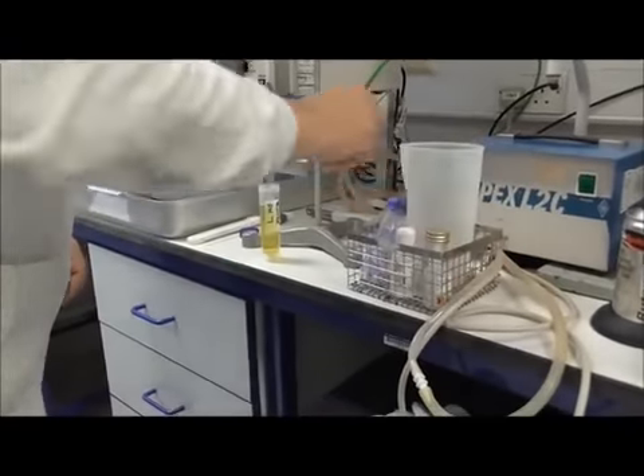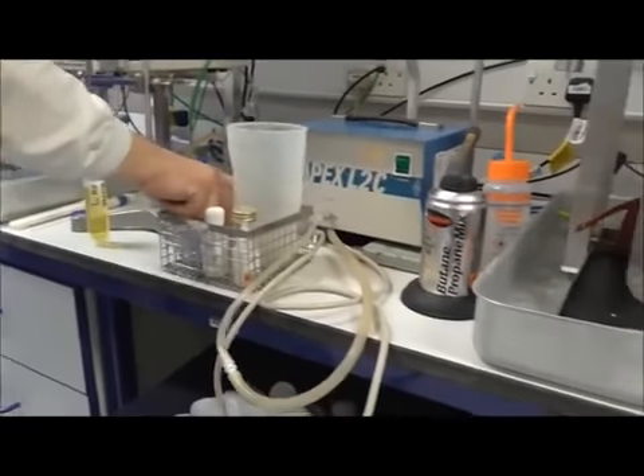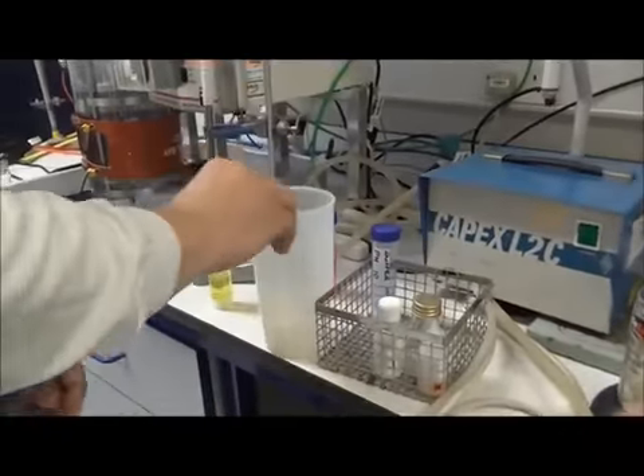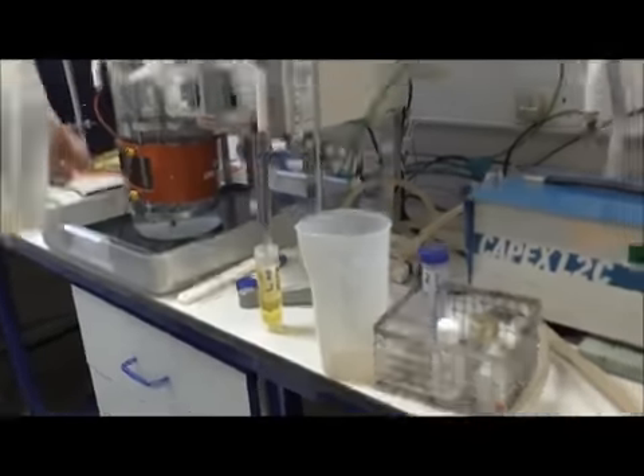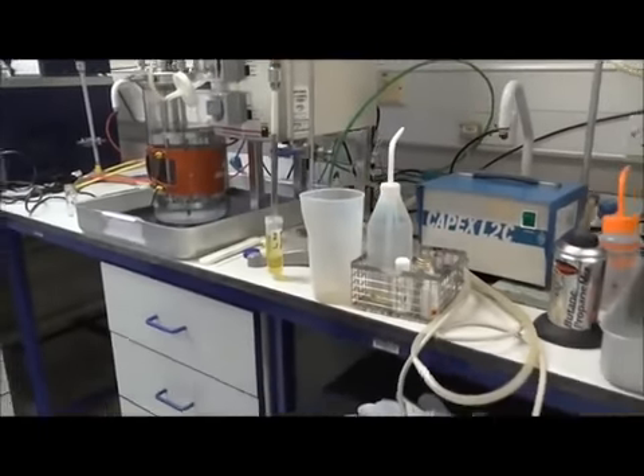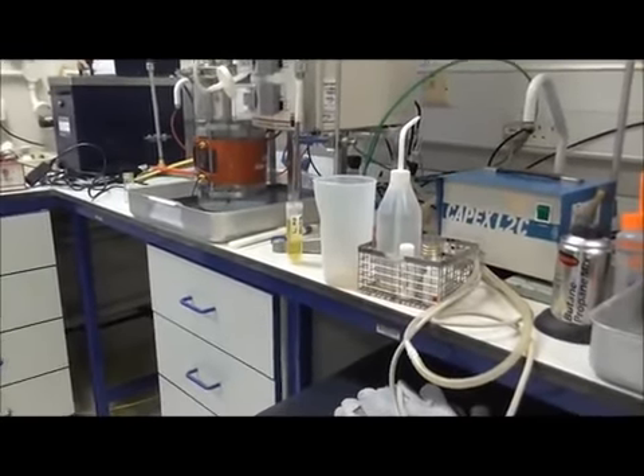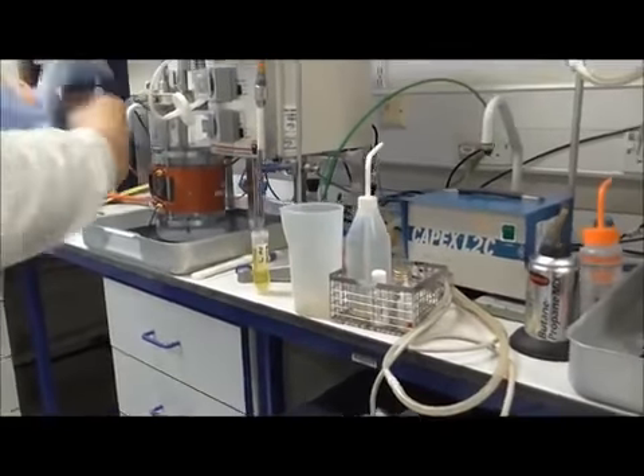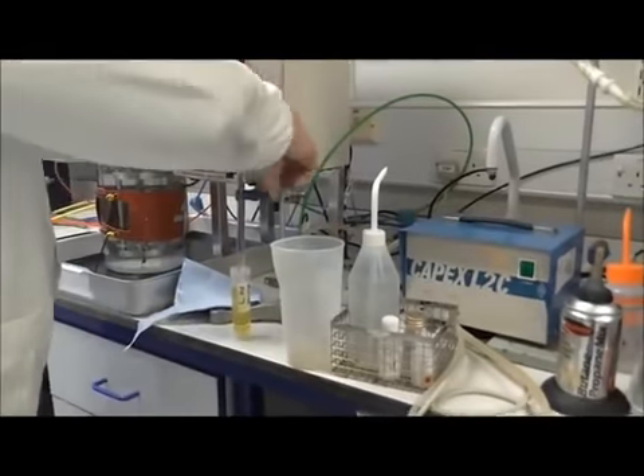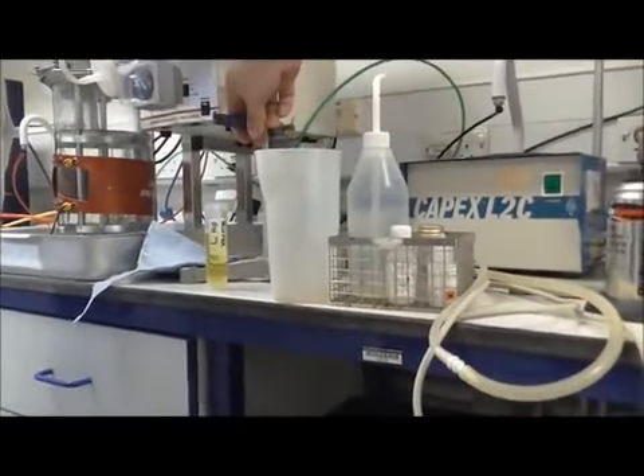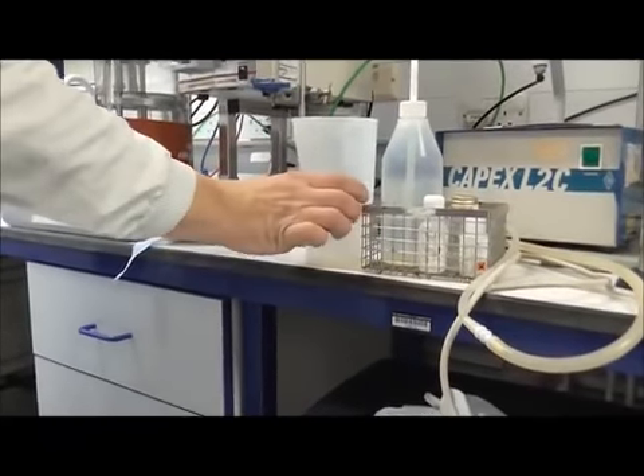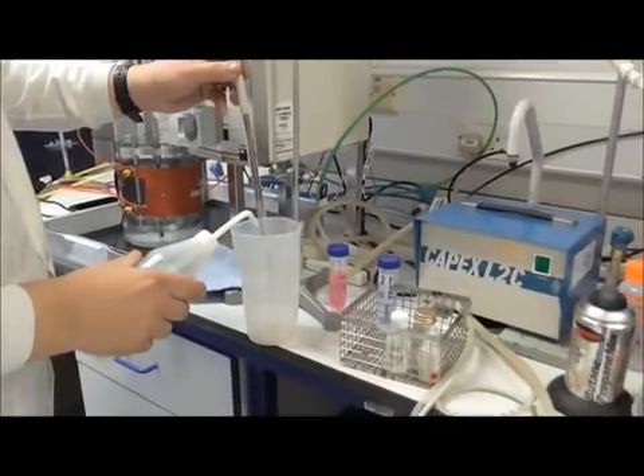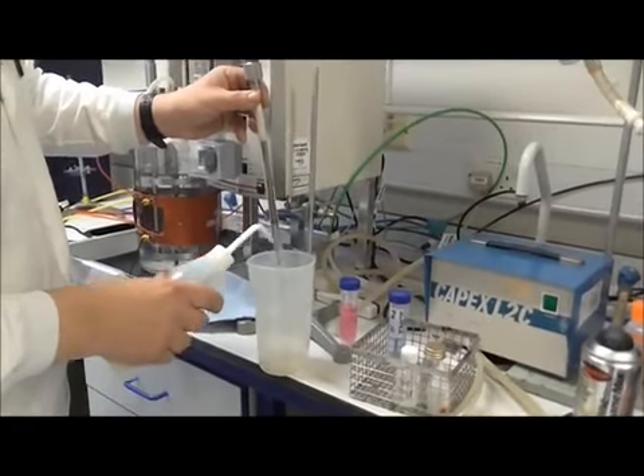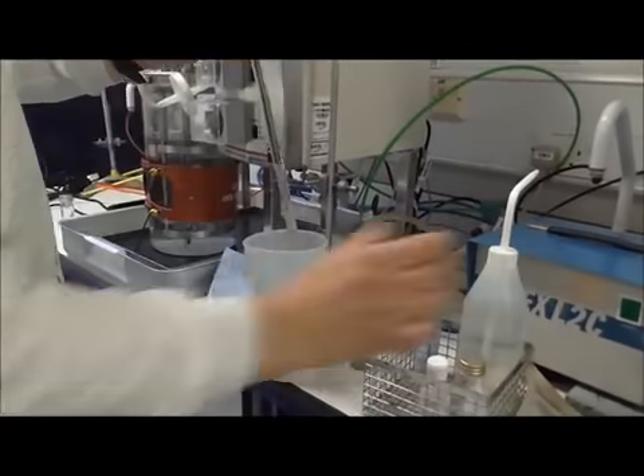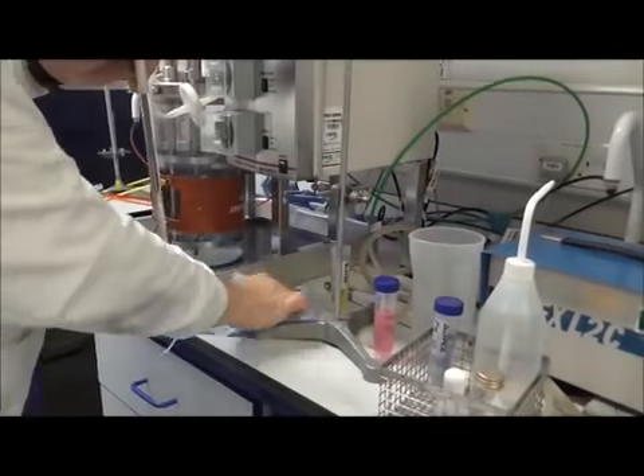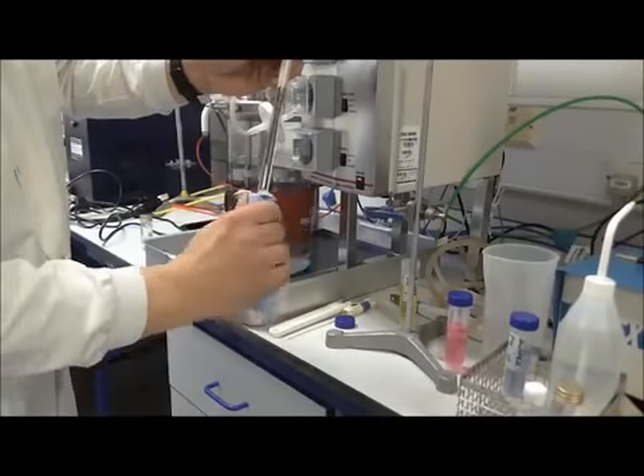Now this is where you need about sort of 3 pairs of hands. So we get our buffer number 4 ready. We have a beaker, and we also have a squirty bottle of distilled water, and we need a bit of tissue paper. So carefully remove the probe from the clamp, lift it up, pop number 7 at the back, bring in our beaker. We just want to wash all trace of buffer 7 off the probe, so give a little flush with the distilled water, let that drain. With the tissue, very gently dab dry.